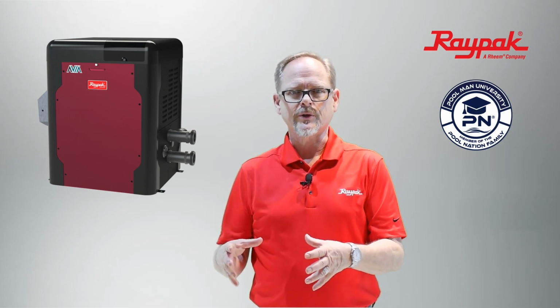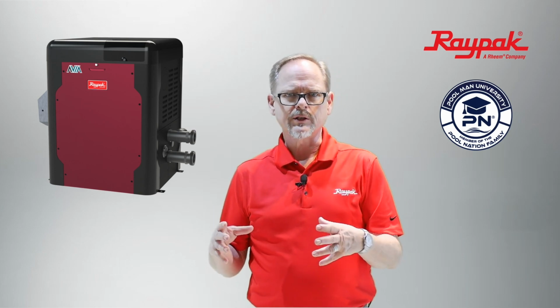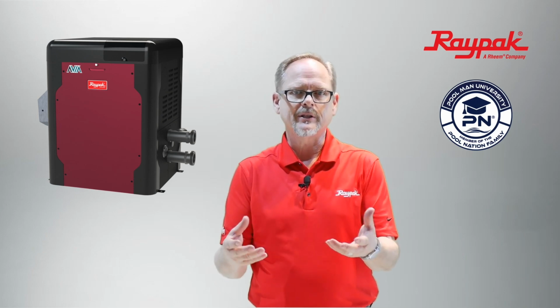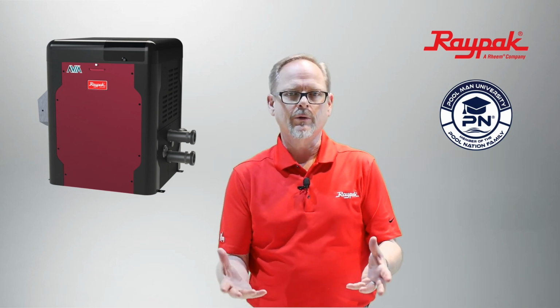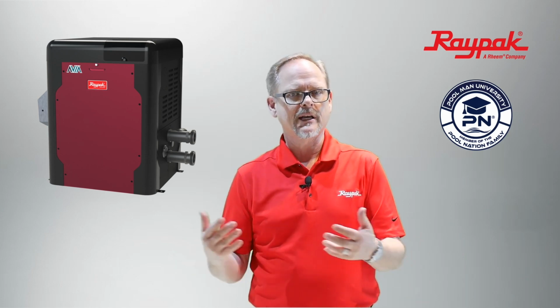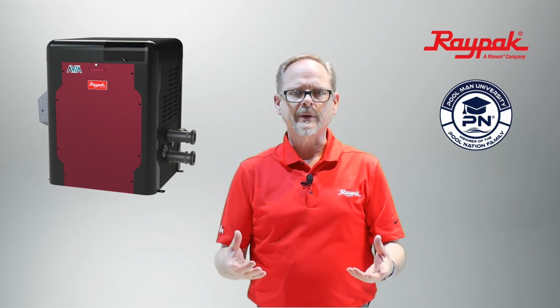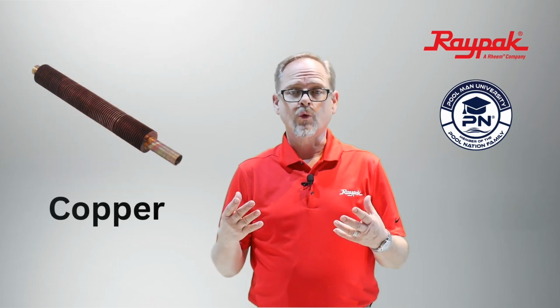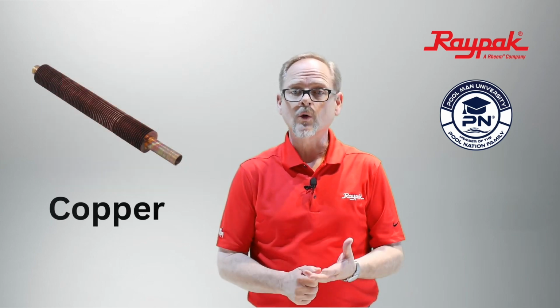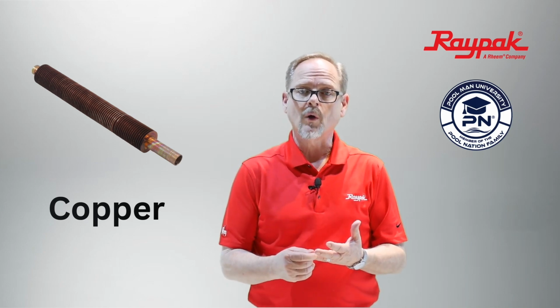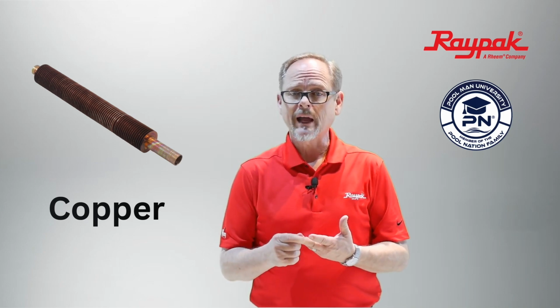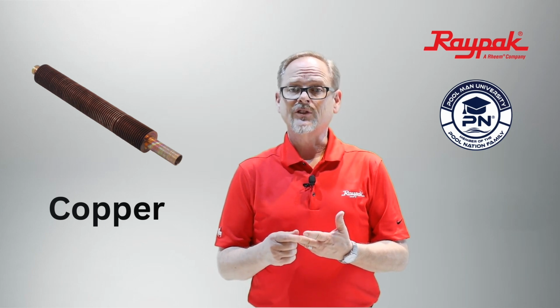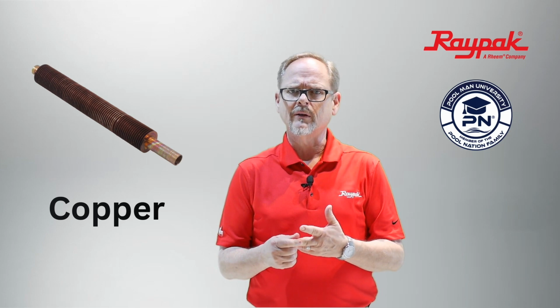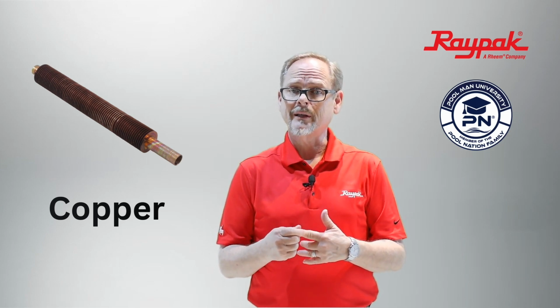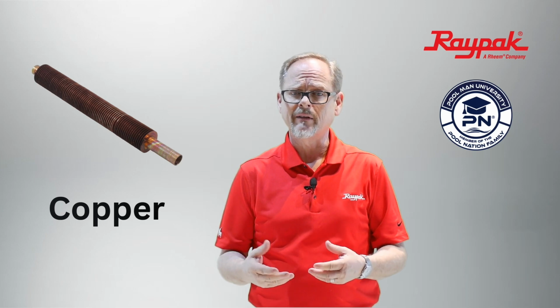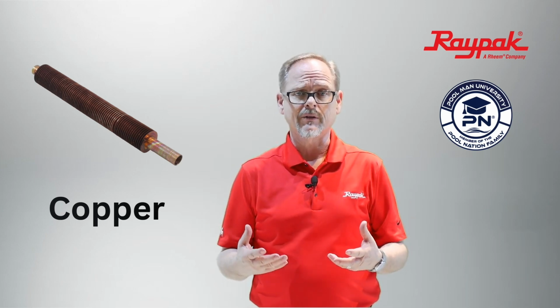In the swimming pool industry, when we heat water by running the swimming pool water through pipes and then burning a fire, above or below those pipes to heat the pipes, and then the water takes that heat back to the pool. Now, these pipes are typically made of copper. Copper is a great metal to use for a heat exchanger. It absorbs heat well. It releases heat well to the water. The biggest problem that we have with copper is that it's soft. So copper is a pretty soft metal, and swimming pool water is typically pretty harsh, or much harsher than the domestic water that you have in your home.